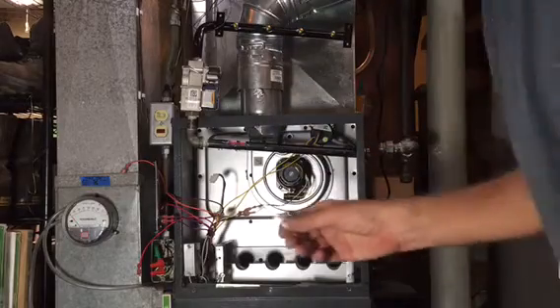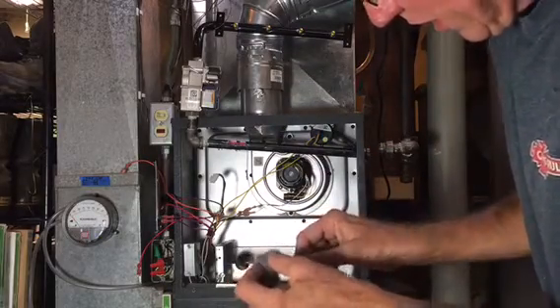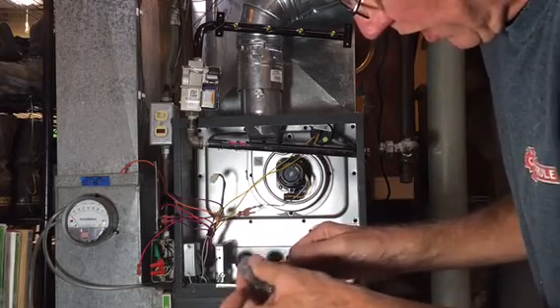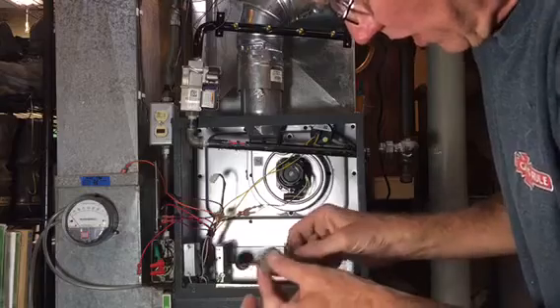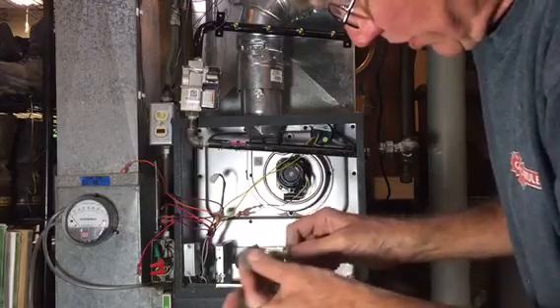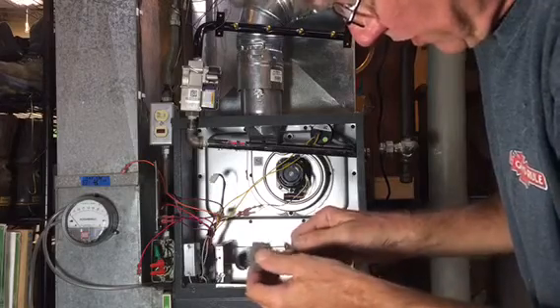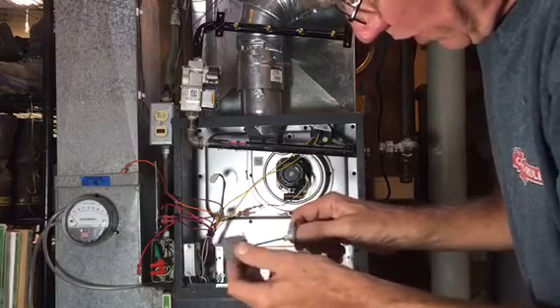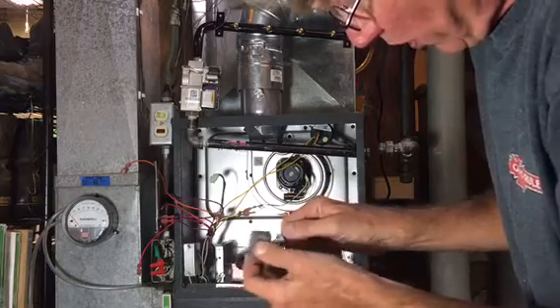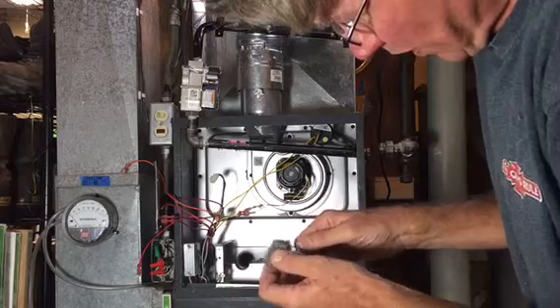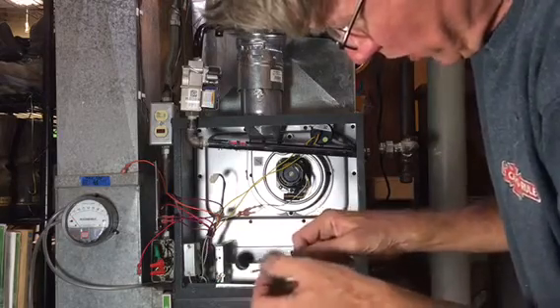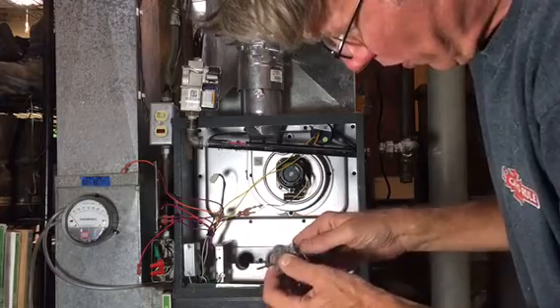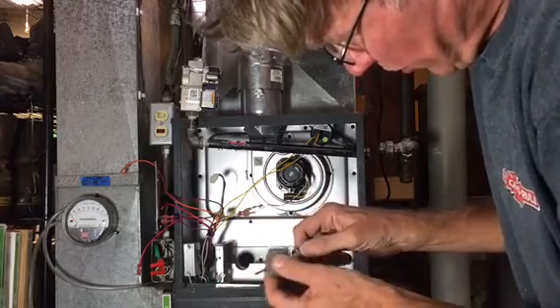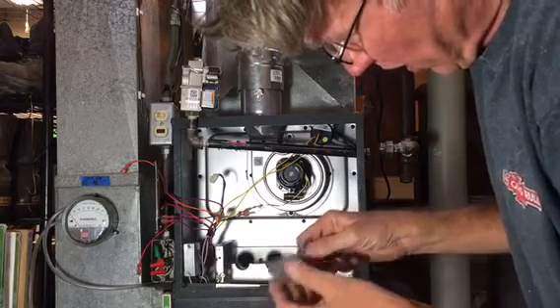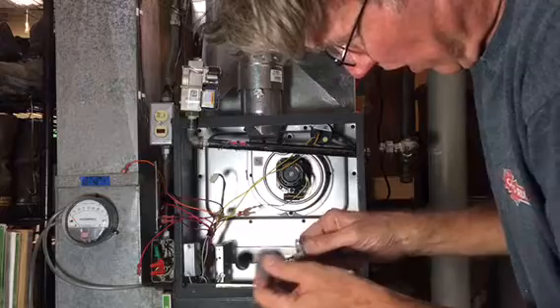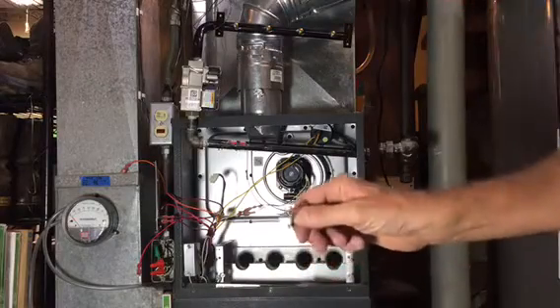Okay. The flame sensor, just very gently. Just clean it. Get some of that oxidation off. Because if this is not sensing the flame, whether due to faultiness or debris, it will not allow the furnace to operate properly. So it's kind of polishing up a little. You don't need it real shiny. I think it's just to get some of the oxidization off, as I said. Okay, that should do it.